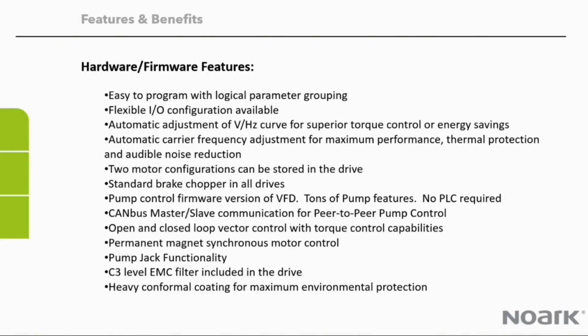We can get you a document that'll talk about those features as well. What this helps is you don't need to add a PLC. You can reduce the cost of your enclosed package by removing the PLC, because a lot of those features are in the drive associated with pumping applications. CAN bus master-slave communication for peer-to-peer pump control. That's for multiple drives working together in a coordinated system. We've developed that inside the drive.